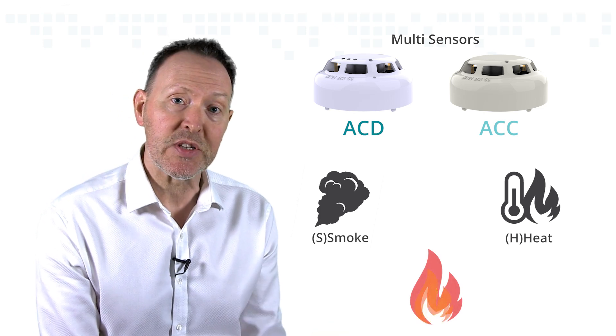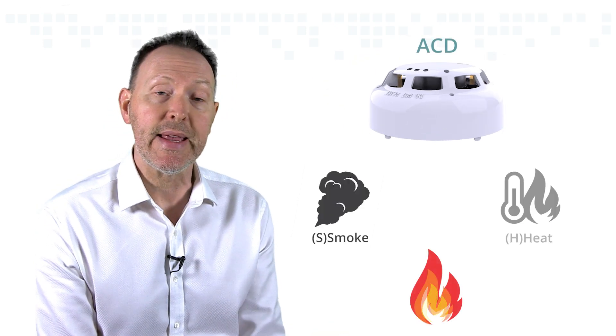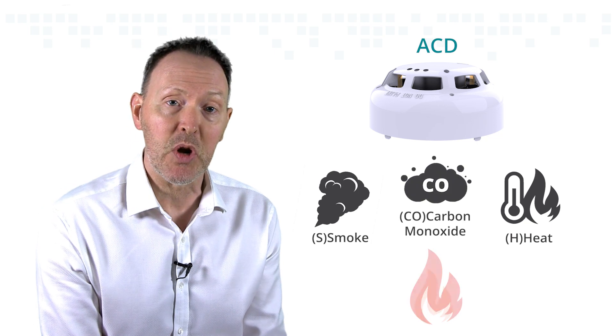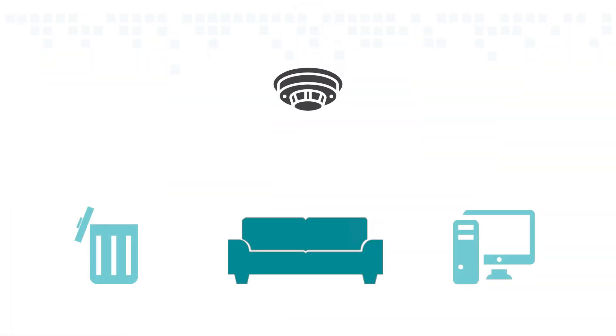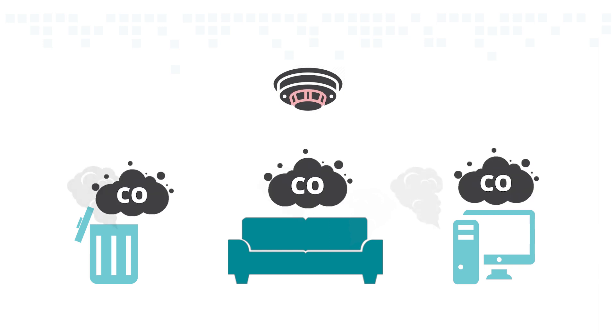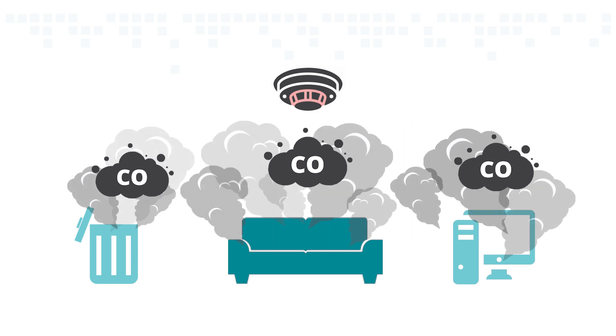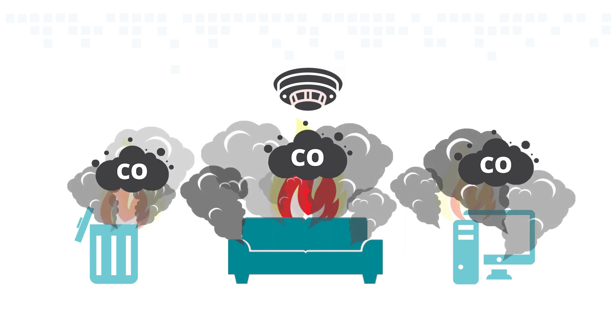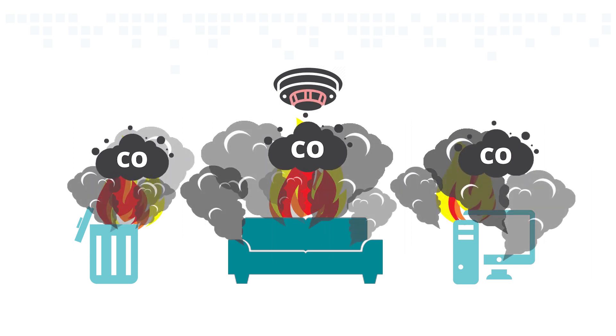But the ACD has been developed with three sensing elements: smoke, heat, and carbon monoxide or CO. Traditionally, CO detection is integrated into a multi-sensor to assist with very early detection of smouldering fires, which release CO gas usually before the presence of visible smoke or flames.